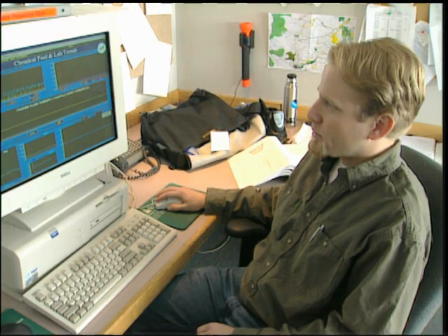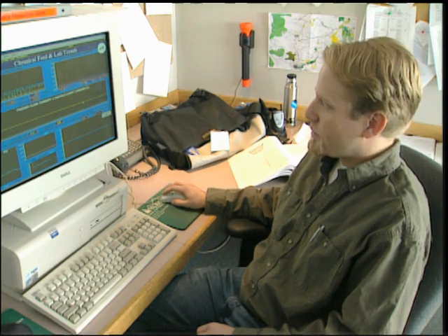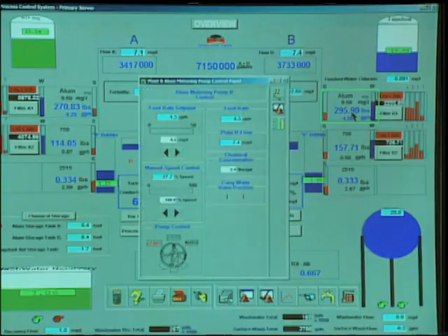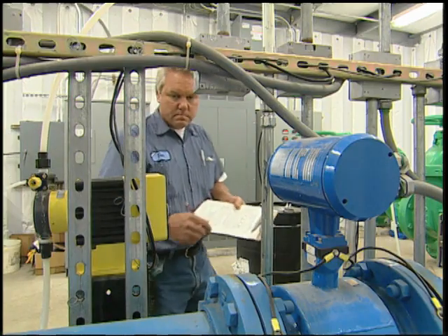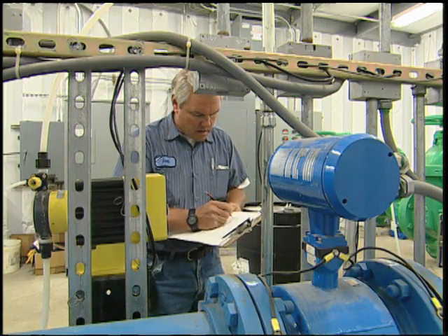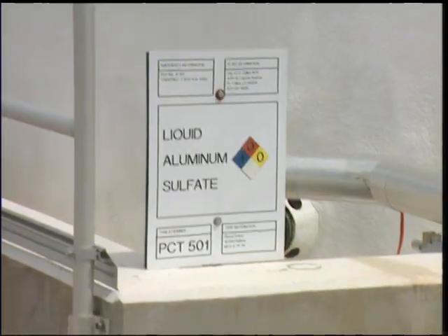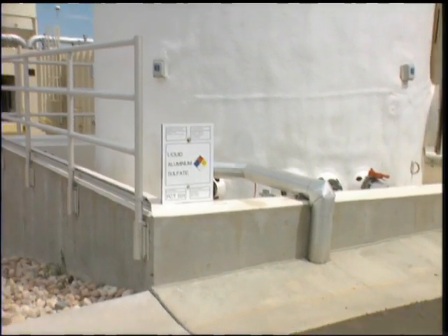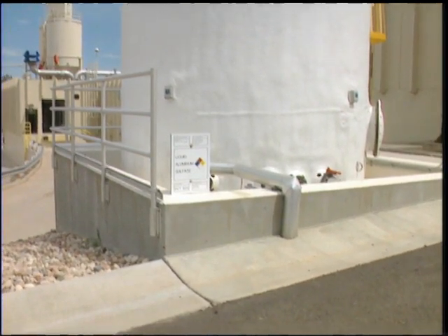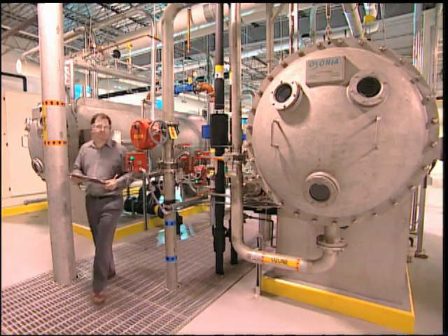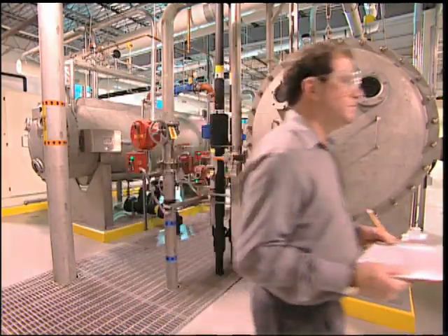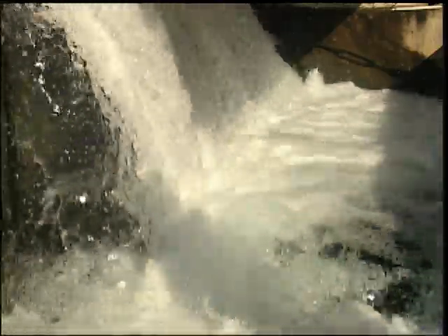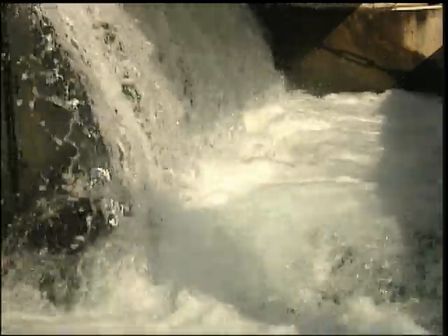In many treatment plant operations, a change in one operating condition produces a proportionate change in some other condition. For example, changing the speed of a metering pump changes the quantity metered, or changing the amount of chemical added to a certain volume of water changes the strength of the solution. If you establish a relation or ratio for a particular condition, then when one of the quantities changes, you can calculate what the new value of the other quantity will be.